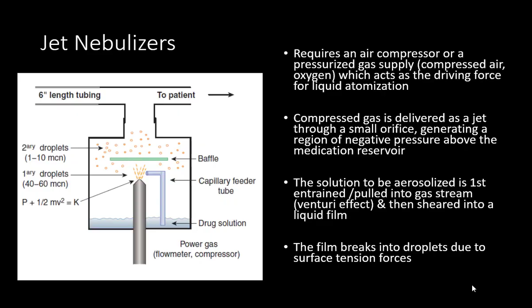So jet nebulizers require an air compressor or a pressurized gas supply. Jet nebulizer is your normal nebulizer. You need at least 6 to 8 liters of gas flow, or a compressed gas coming from the compressor, which acts as a driving force. This compressed gas is passed through a small orifice. You are trying to create a Venturi effect. The compressed gas is delivered as a jet through a small orifice, generating a region of negative pressure and pulling in your gas stream by the Venturi effect. The liquid film then breaks into droplets due to surface tension forces.